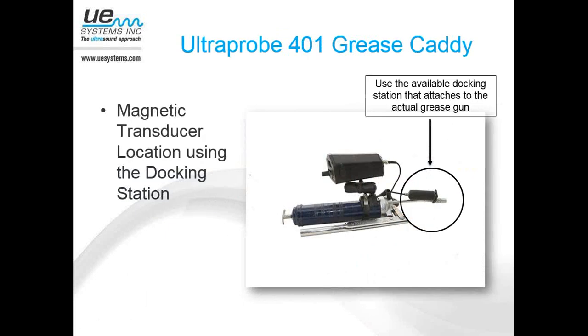Okay, so when it comes to the location where we want to put that magnetic mount contact probe, if you've been through any of our training classes, obviously the closer we can get to the bearing as possible, that's going to be the preferred location. Along those same lines, the nature of high-frequency sound is that it doesn't travel very far from the source, so the further we get away from that bearing, the more that sound is going to attenuate and we can drop in decibel level. So ideally, the closest point to the bearing as possible is going to be preferred.